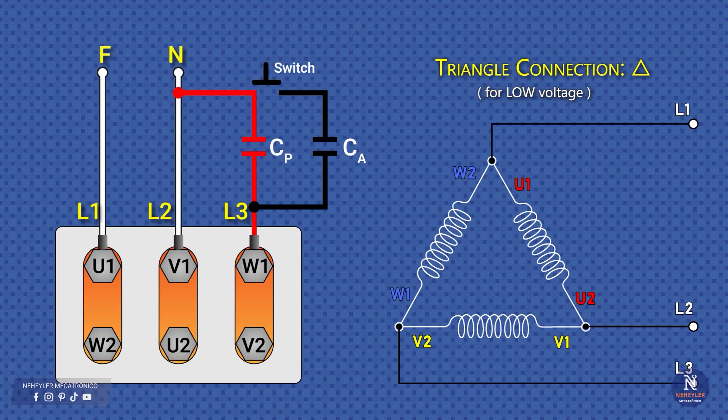In delta connection, the end of each winding is joined with the beginning of the next. U1 with W2, V1 with U2, and W1 with V2. The supply is applied at the three corners, and at one of these the capacitors must be connected to the single-phase line. This connection is used for low voltage.